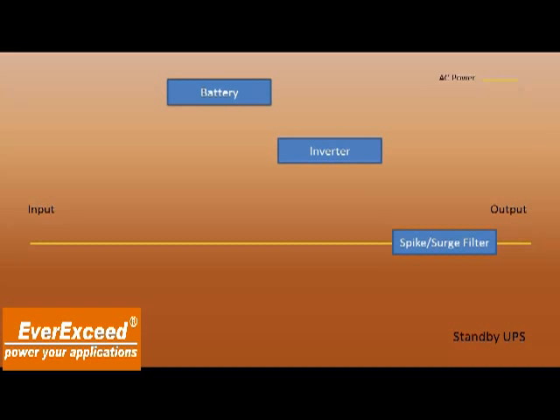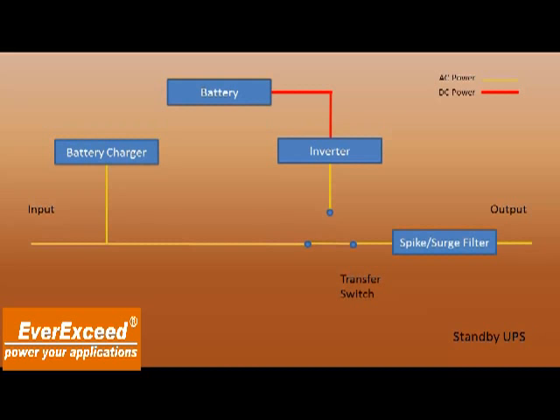We'll start with a battery and an inverter to convert that DC voltage from the battery to AC. We'll put a transfer switch in line. Connect that to the inverter. Put in a battery charger to charge the battery. Connect that to the power coming in and connect that to the battery. Put in a control circuit.